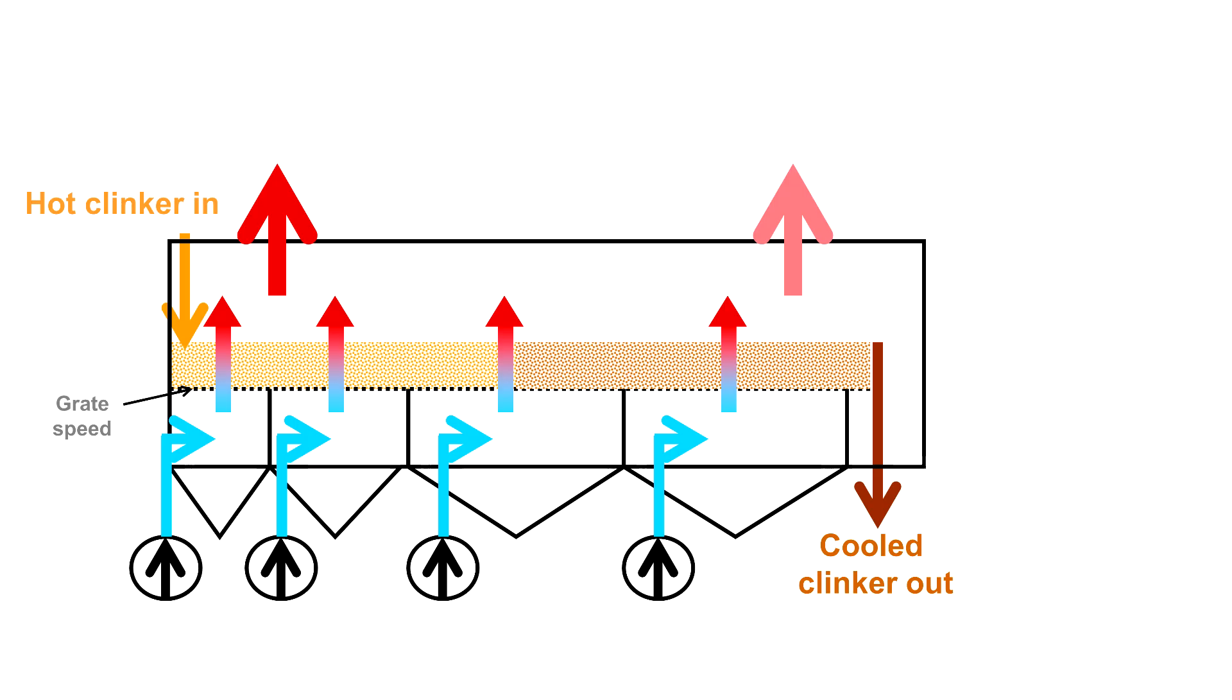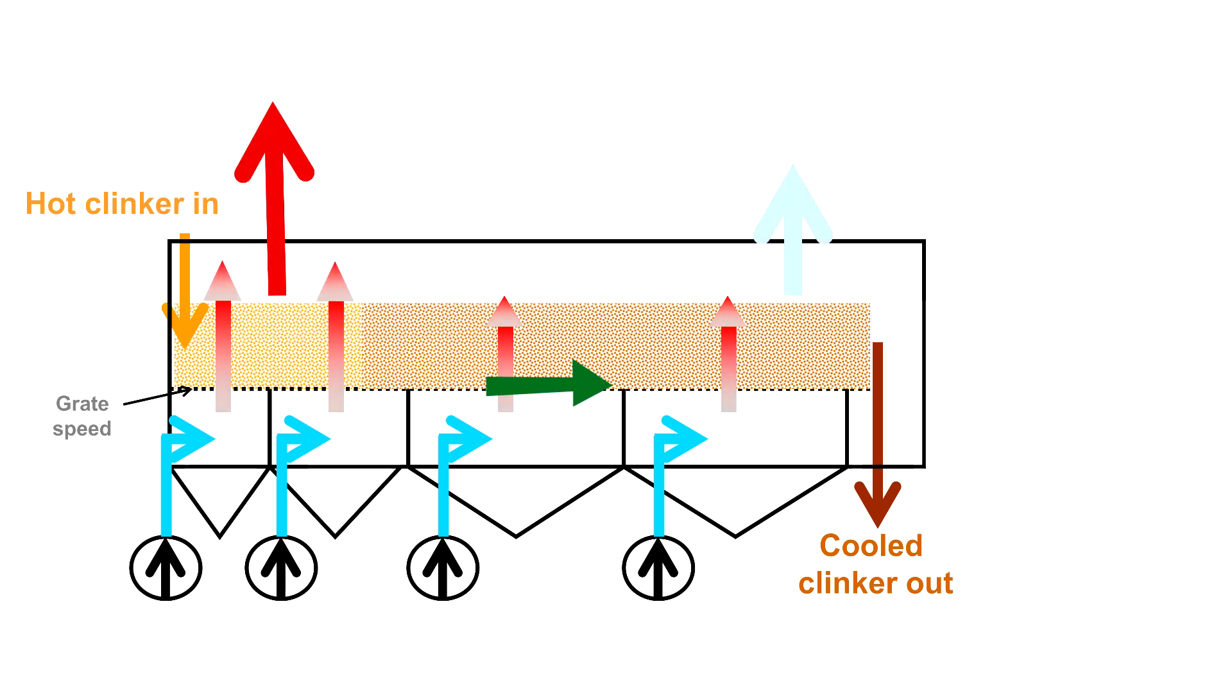Knowing this and looking at the previous scheme, this means that in theory, the best way to run the cooler would be to have a very slow grate speed, which would keep the hot clinker in the recuperation zone and achieve the best heat exchange possible. This is the theory. But let us understand how much energy can be recovered from hot clinker. Let us talk about the cooler heat balance.